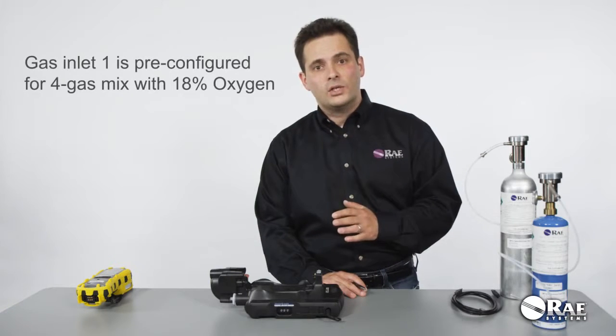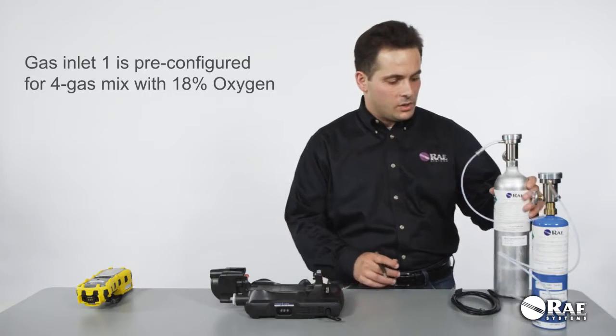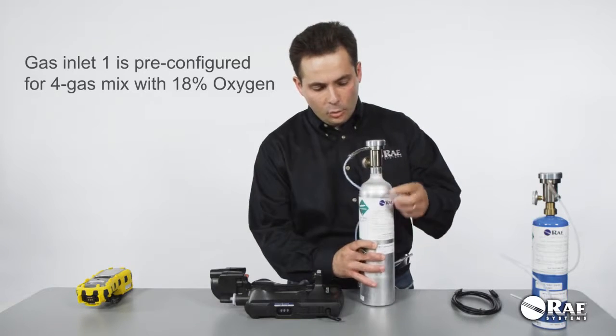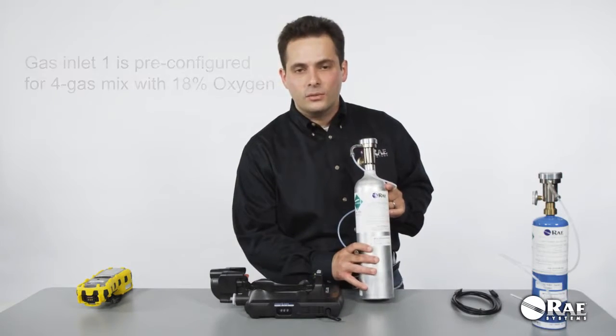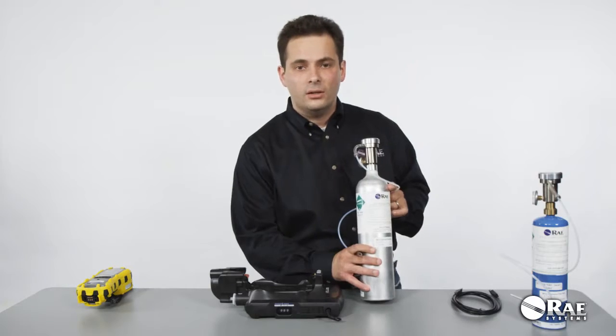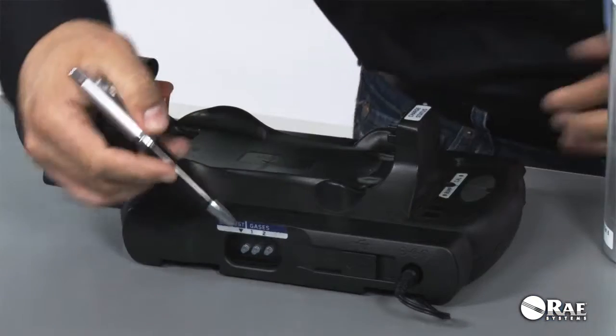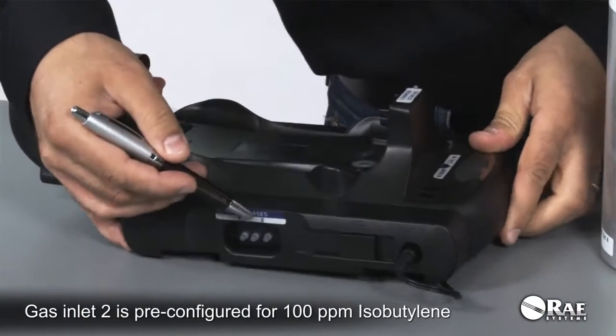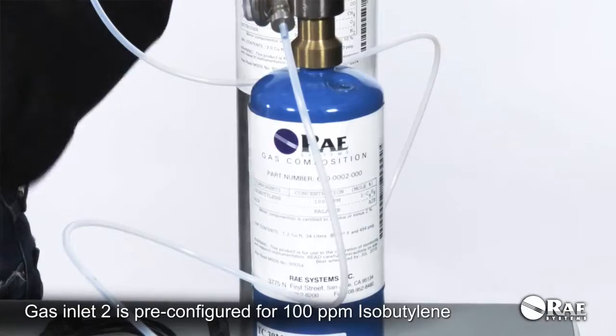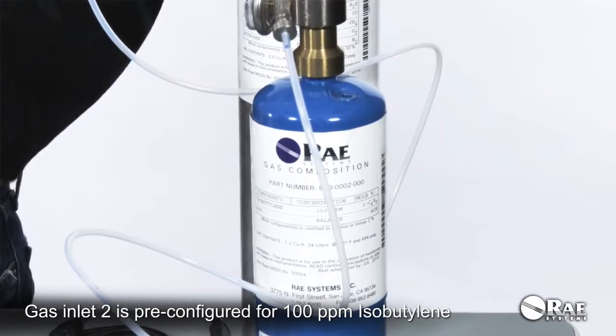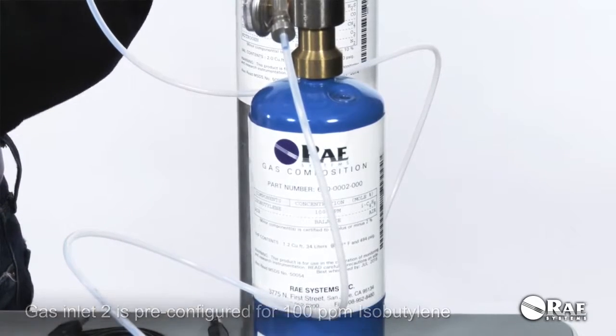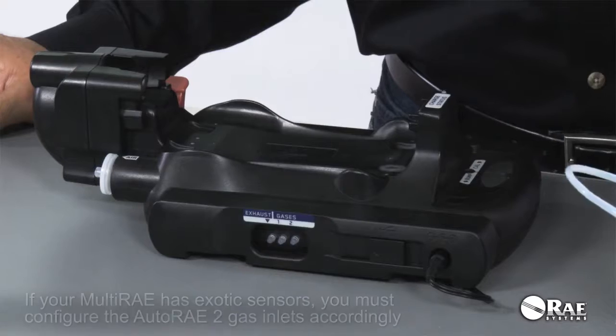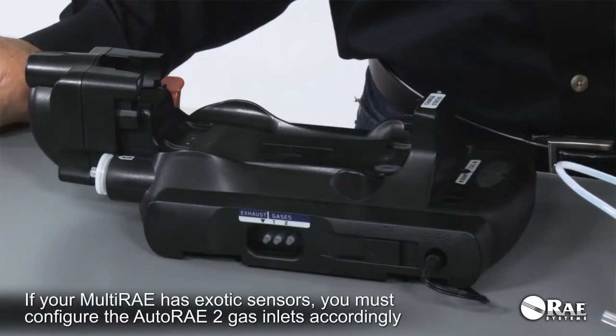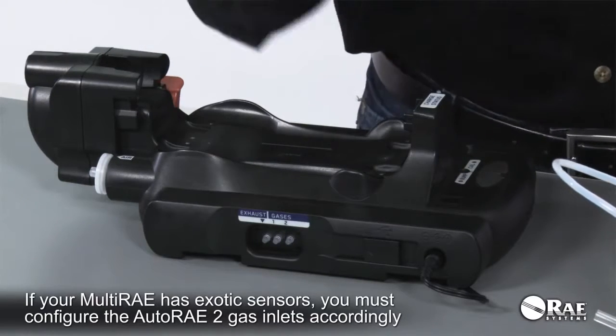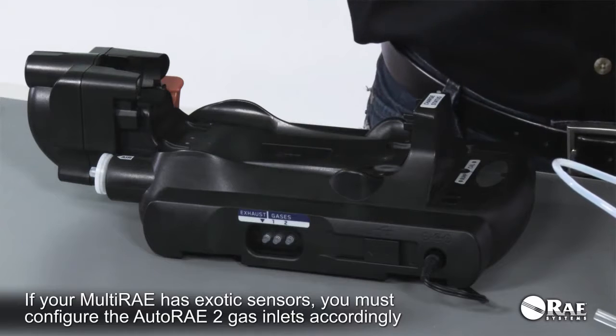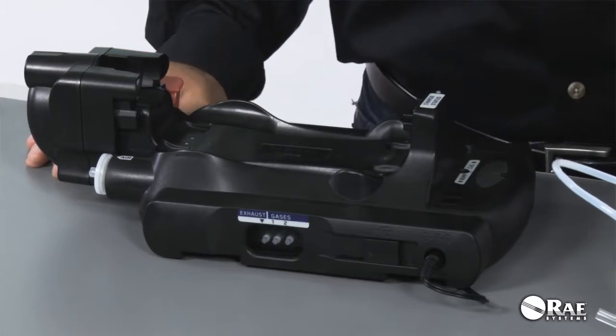Gas inlet 1 is configured for a 4-gas mix that is used to calibrate the 4 sensors, CO, H2S, O2, and LEL. And the second inlet is configured for isobutylene that's used to calibrate the PID sensor. It is critically important to make sure that if your MultiRAE has exotic sensors in it, you configure the inlets to match the calibration gas that you're going to use for these exotic sensors.